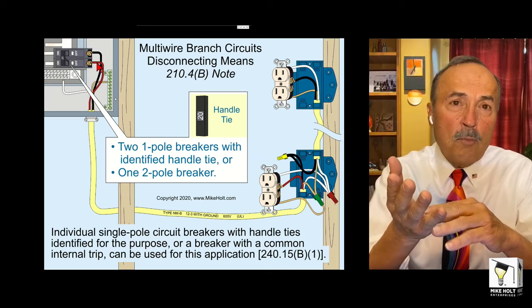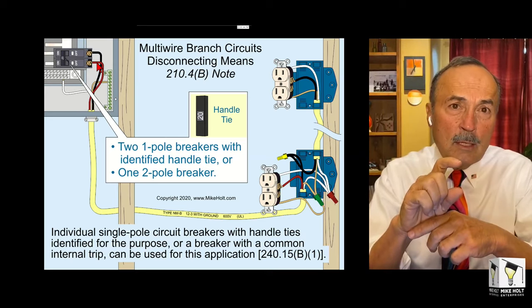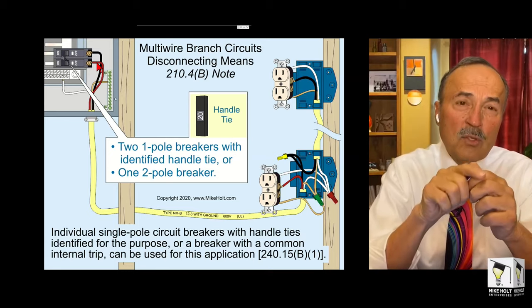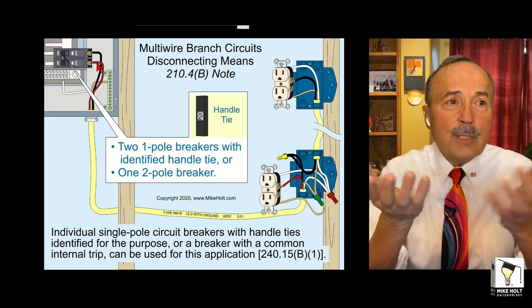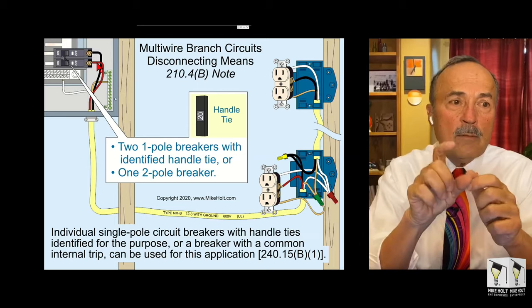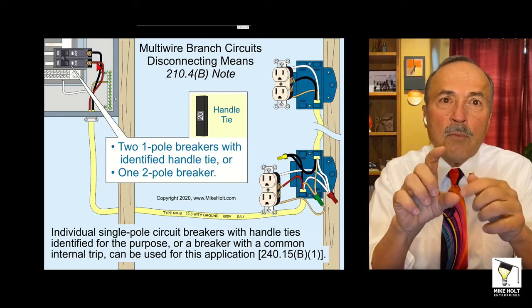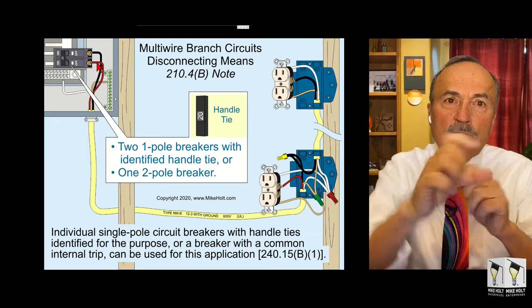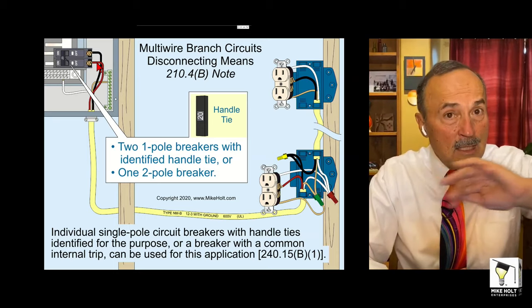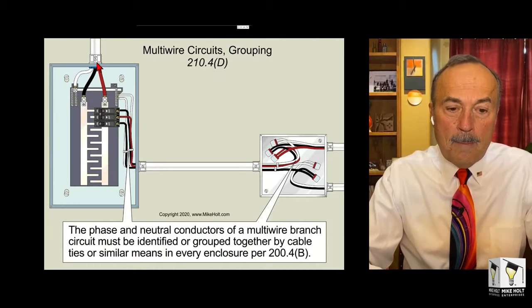But if you take single pole breakers and you put handle ties in between them, particularly Square D, if you put that little pin in between like that, one will trip and the other one won't. Or you've seen these twin breakers with the little tandem connections. That's okay because it's a simultaneous disconnect.